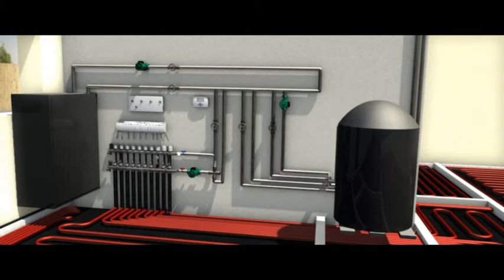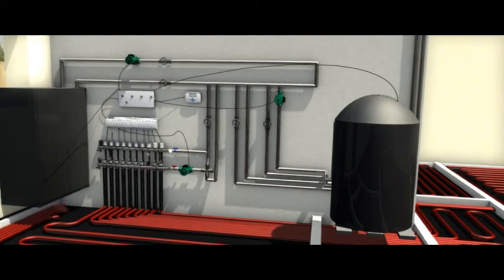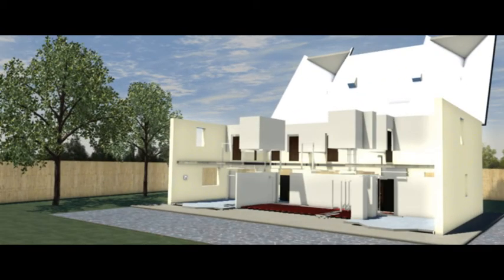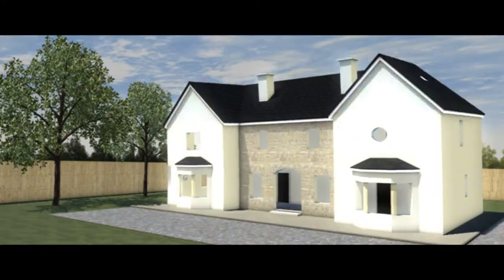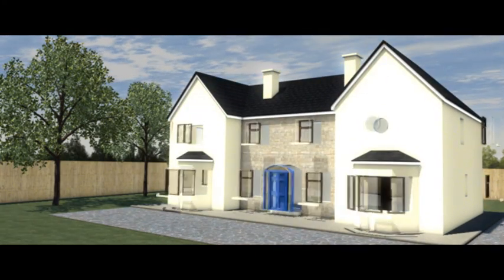To wire the system, all thermostats and their corresponding actuators are wired into the top and bottom of the wiring center. Next, the underfloor pump will be wired out of the pump connection on the center. Now the wiring center is connected to the heating control panel, followed by the primary pump, the boiler and the time clock. The wiring is completed by connecting the cylinder pump and thermostat to the corresponding connections on the panel. The upstairs underfloor system is wired in a similar manner, but will use the downstairs heating control panel.